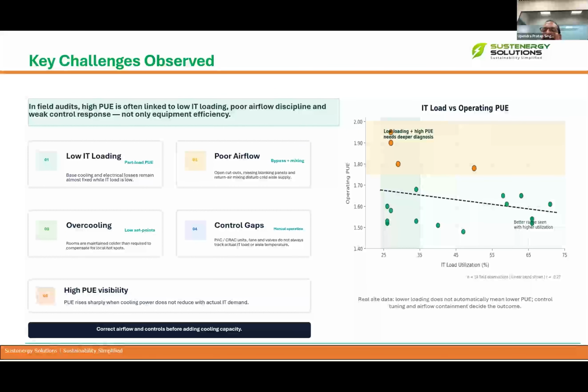Then the second lever is airflow. Airflow management is also very important in data centers. When we do the studies, we find that sometimes there is cold air, hot air mixing. Or if you see some older data centers, even racks are not arranged properly. So we need to make a proper hot aisle, cold aisle arrangement. Now most people are aware and they are doing it, but still there are some facilities where you will find that there is a mismatch. Hot aisles and cold aisles are not properly designed and there is mixing that we need to address.